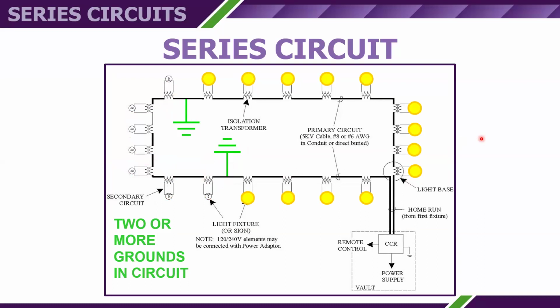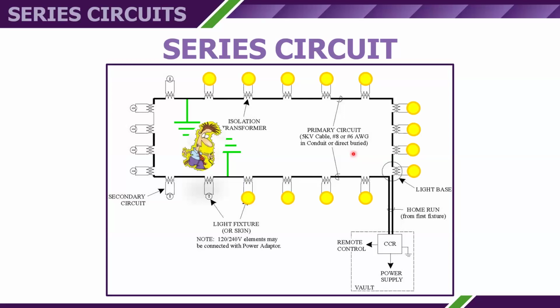For troubleshooting, the problem is probably between the last two operating fixtures. And you do not want to dig while that circuit is energized. You also want to make sure that you do not become part of that circuit, getting between the grounds.